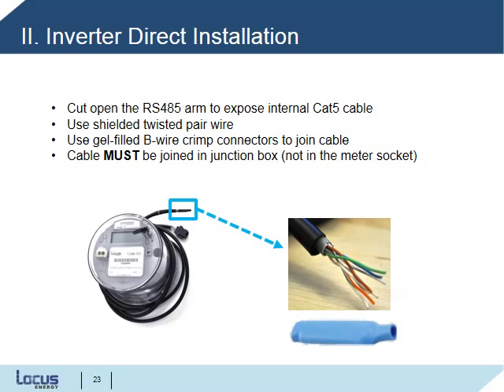Now, if you're considering inverter direct monitoring, here's how to set up that connection. First step is to cut the heat shrink wrap off the RS-485 arm to expose the internal Cat5 cable. Next, use shielded, twisted pair wire to connect this cable to the inverter. Always join cables using gel-filled B-wire crimp connectors. And be sure to join the cable in a junction box and not within the meter socket. RS-485 cable should always run in separate conduit from high voltage AC lines.